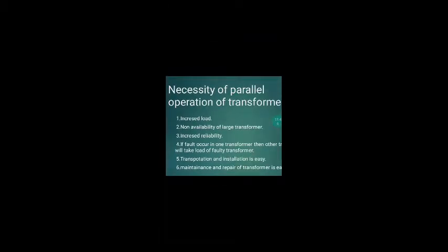Then, non-availability of a large transformer. See, if a large transformer is not available, for example, if you don't have a 1 MVA transformer, then you can connect two 500 kVA transformers in parallel.